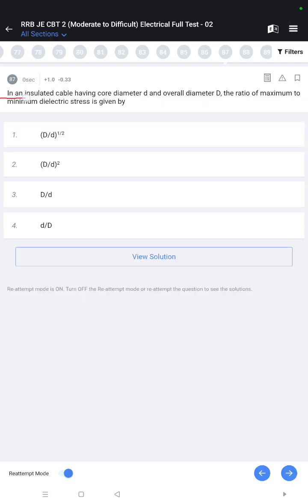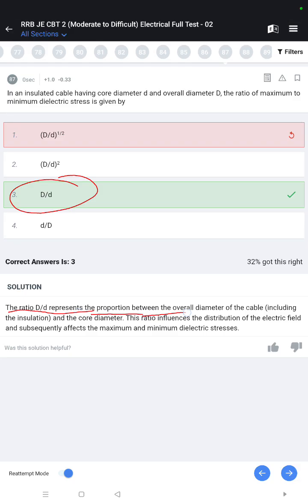In an insulated cable having core diameter small d and overall diameter capital D, the ratio of maximum to minimum dielectric stress is given by capital D बटा के small d. The ratio of capital D to small d represents the proportion between the overall diameter of the cable including the insulation and the core diameter. This ratio influences the distribution of the electric field and subsequently affects the maximum and minimum dielectric stress.